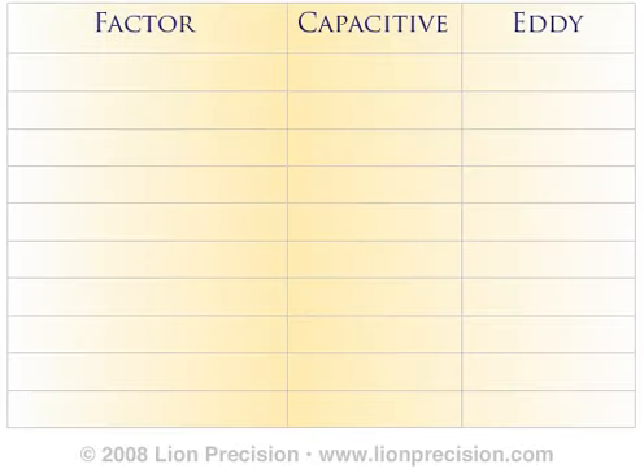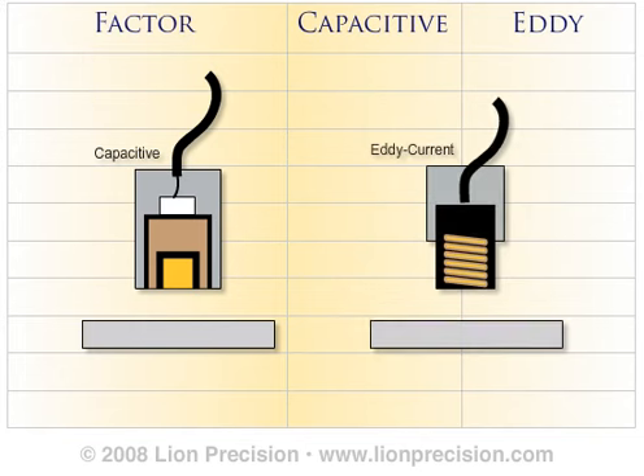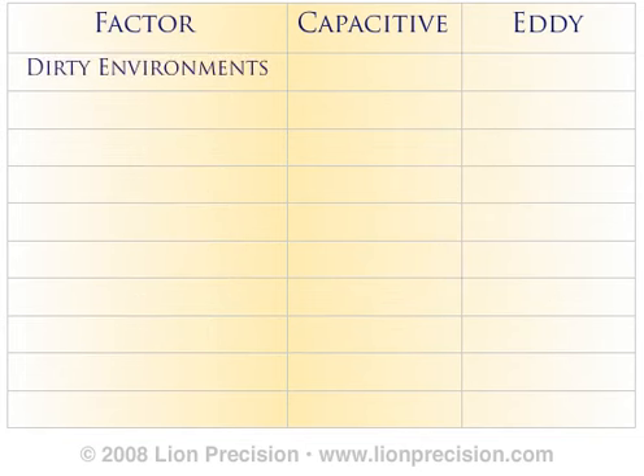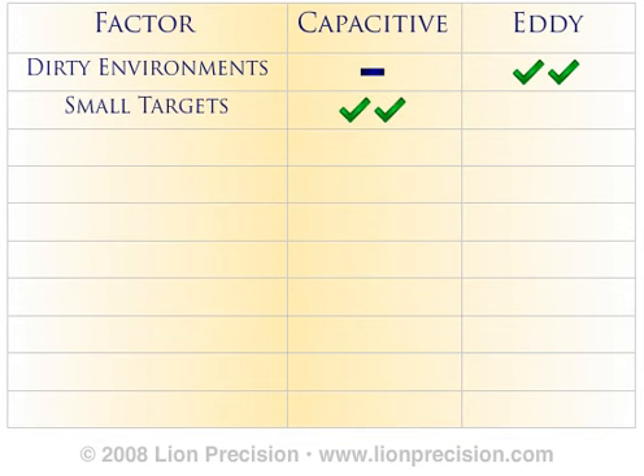As you can see, there are many factors to consider when choosing between capacitive and eddy current displacement sensors. Any application that involves measurement area contaminants, such as liquids or waste material, requires eddy current sensing because capacitive sensors require a clean environment. Small targets will be more easily measured with capacitive sensors because of the comparatively small size of the capacitive sensing field. When eddy current sensing is required, special calibration can be used with small targets.